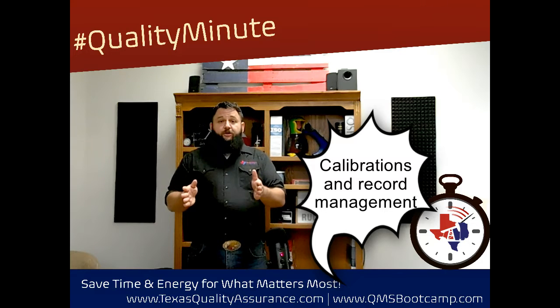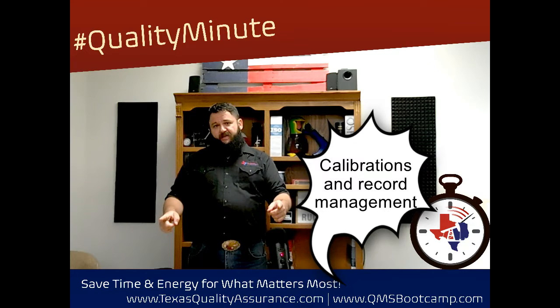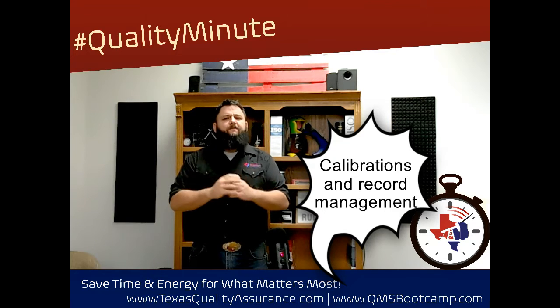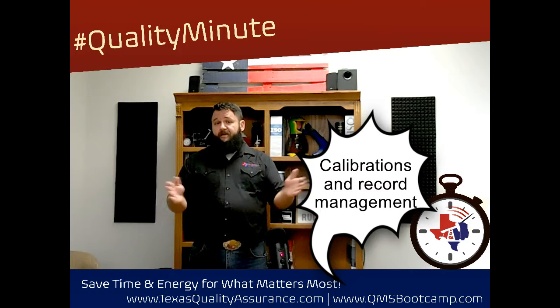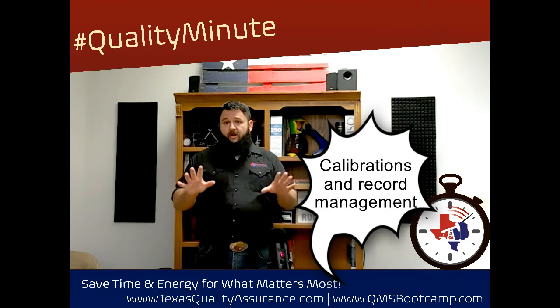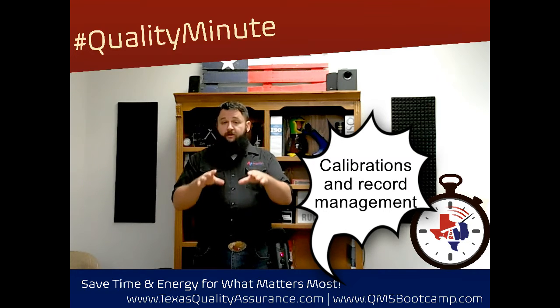So with these, there's all sorts of options available depending on what you're using, from pyramid blocks, where maybe it's 12 inches at the outer diameter, 1 inch at the top. You can check ID on some, and OD and everything else. There's just plenty of options available here, and in a variety of sizes. What you need to do is get the appropriate set of blocks for the tools that you have available in your organization. Then you're going to want to set up your own calibration tracking method for these.